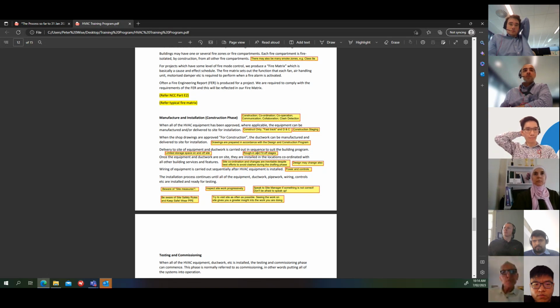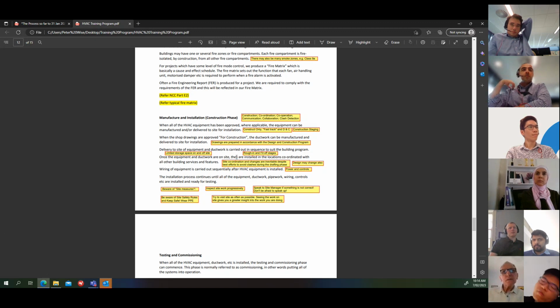Once that's all done, you go to the fit-off stage, which is the work below the ceiling. So putting in air outlets, grills, temperature sensors, all of the stuff you can see when it's finished. Once the equipment and ductwork are on site, they're installed in locations coordinated with all the other building services and features.